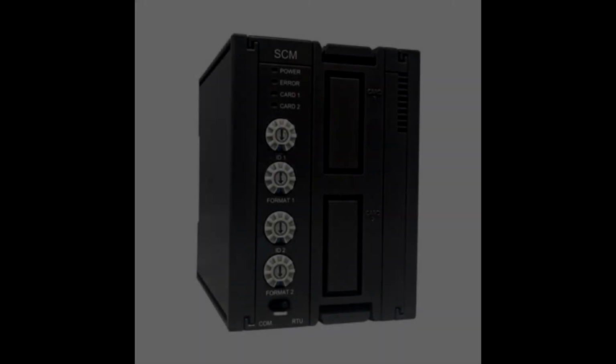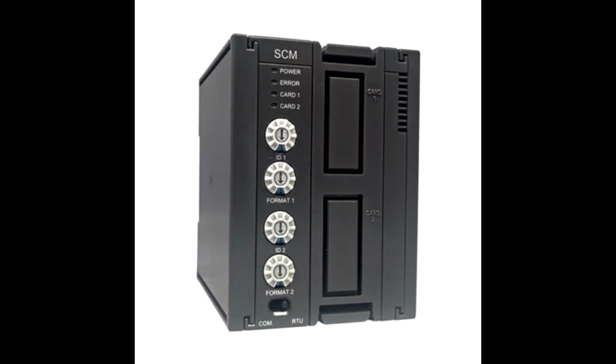On the AS00SCM module, there are 4 rotary knobs and a selector switch available for configuration. The selector switch is to declare if the module is used as a communication module connected to the right side of the CPU or as a remote communication module. In this example we will be using it as a remote communication module, so you can switch it to RTU.